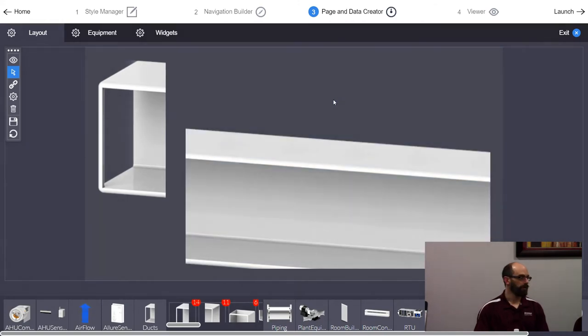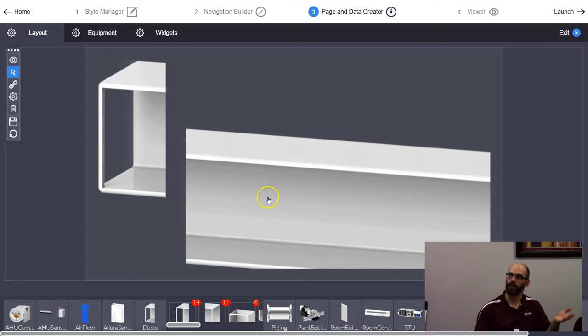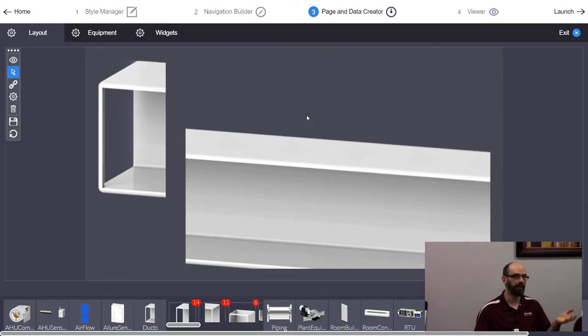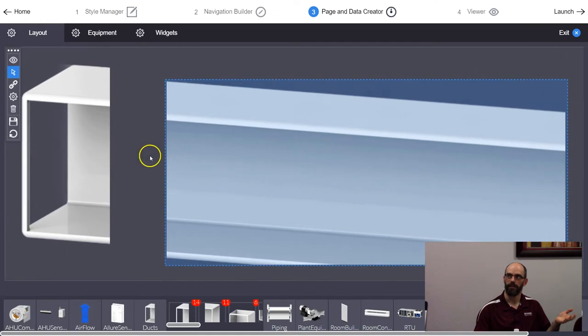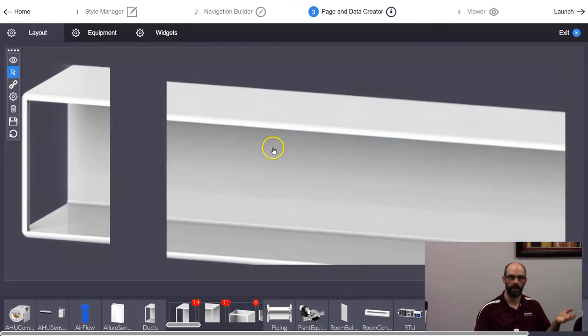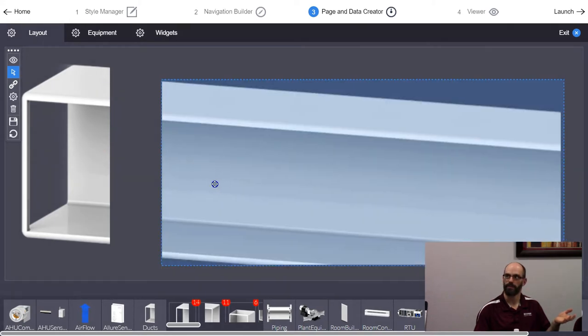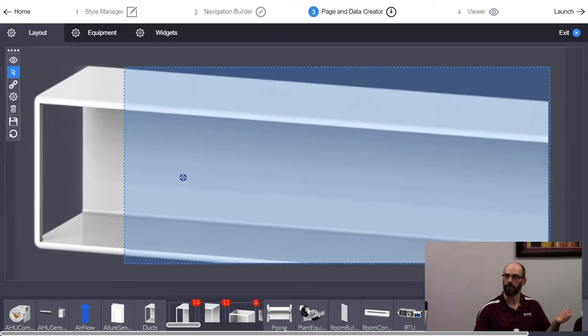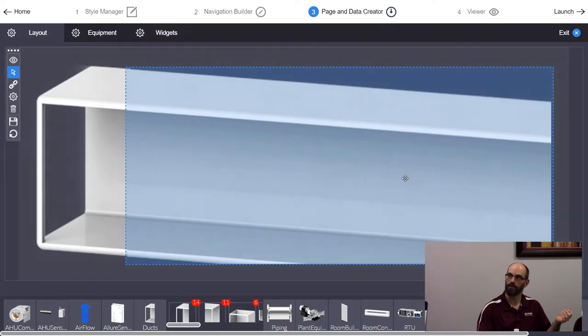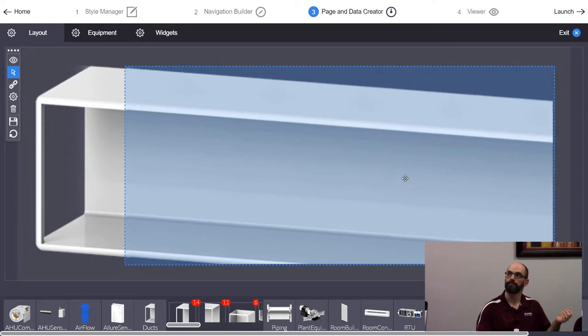Something important when you're in web editing — different from Niagara 4: if you click and drag without first selecting an item, it won't move. Since it's a web editing tool, you have to select what you're on first, then drag it. If you don't select it first, it'll drive you crazy because you can't figure out why stuff won't move. Once selected, you can also use arrow keys to bump it into place.